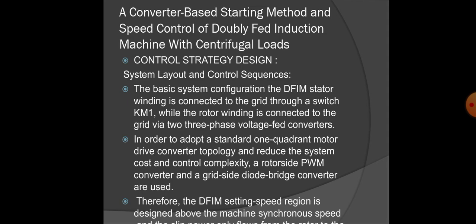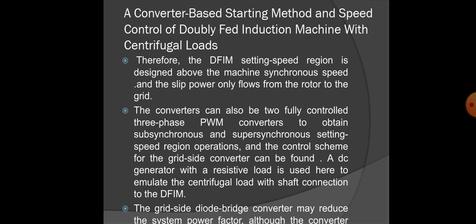And therefore the double fed induction machine setting speed range is designed above the machine synchronous speed, and the slip power can only flow from the rotor to the grid. The converters can also be fully controlled 3-phase PWM converters to obtain the subsynchronous and super synchronous setting speed range and operation, and the control schema for the grid side converter can be found.